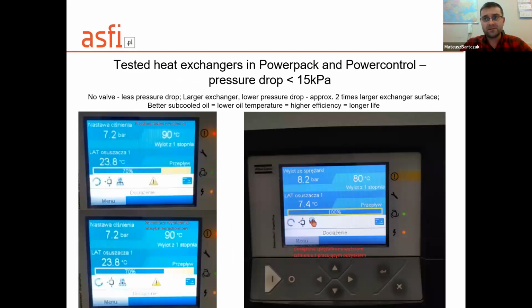I just talked about the pressure drop on the heat exchanger. I will also mention the pressure drop on the control valve at the same heat exchanger. The pressure drop on this valve is also between 30 and 100 kilopascals. It has to have a large pressure drop to maintain linear flow control. So the total pressure drop on the exchanger and valve set is between 1 and 2 bars.